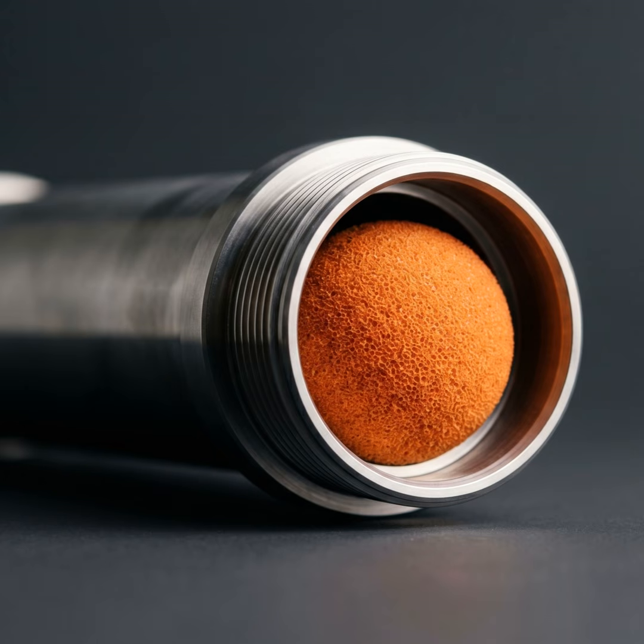So a small portion of the water in the tower evaporates, pulling an immense amount of heat away in the process. And then what happens to the rest of the water? The now cooled water collects in a large basin at the bottom of the tower and is sent back down into the basement chiller to repeat the endless cycle. It is essentially the exact same biological mechanism the human body uses to cool itself by sweating. It's not the sweat sitting on your skin that cools you. It's the phase change, the evaporation of that sweat into the air that pulls the heat away from your body.